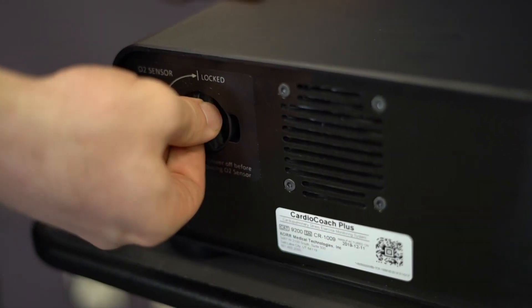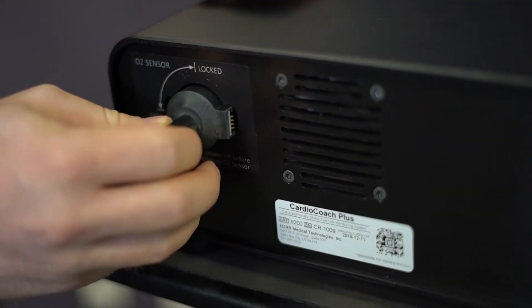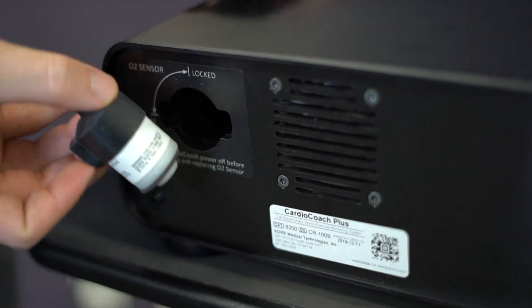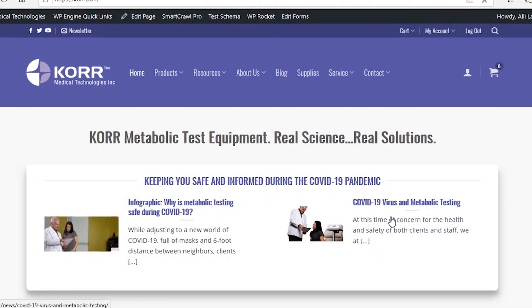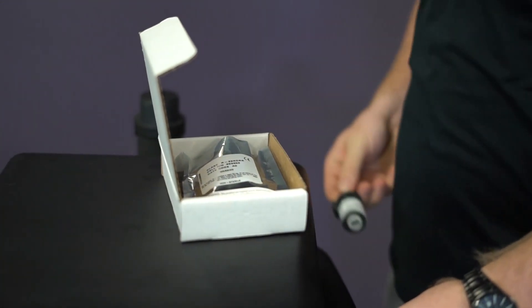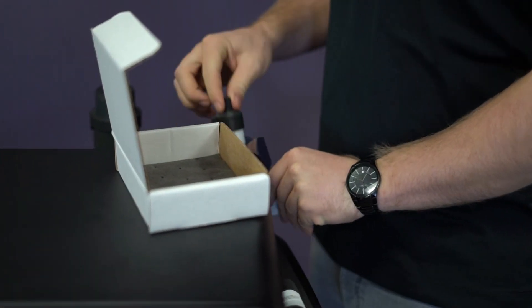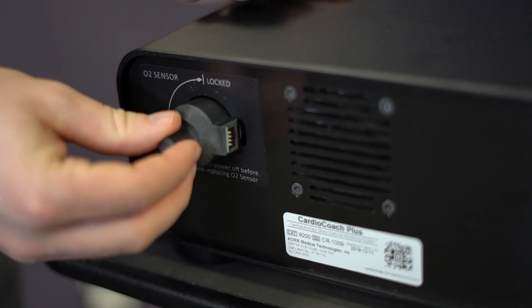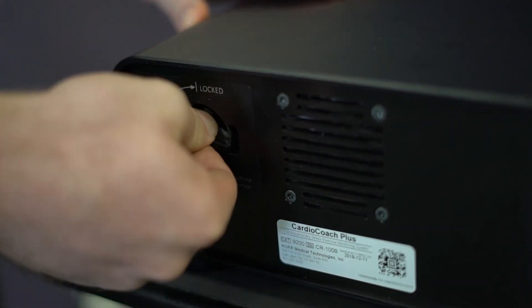KORR measurement equipment relies on oxygen sensors that have a lifespan of 18 to 24 months regardless of usage. When that sensor expires, you will need to order a new sensor directly from KORR at www.korr.com. Oxygen sensors may expire without warning. It can be inconvenient and frustrating to have testing services interrupted when your device unexpectedly displays an error code. For that reason, we recommend you proactively replace your O2 sensor every 18 months to avoid unplanned interruptions in usage.